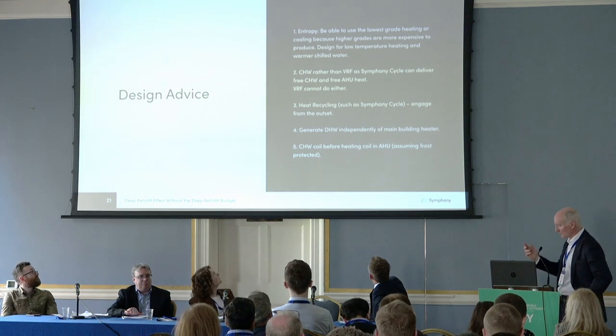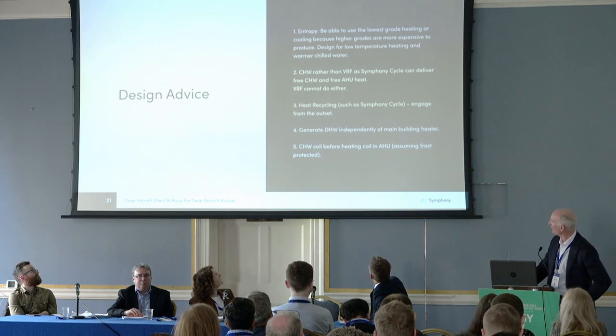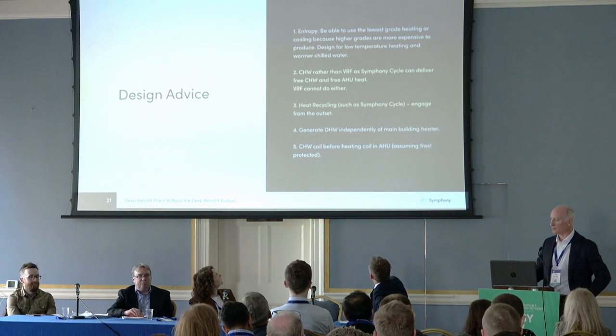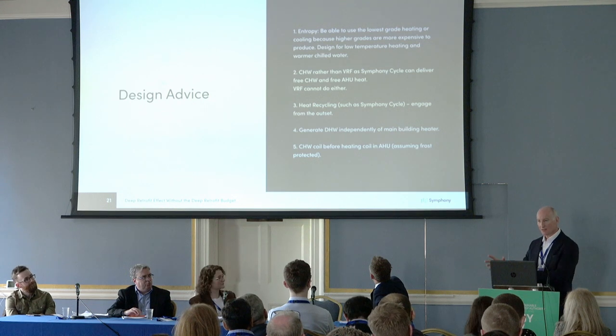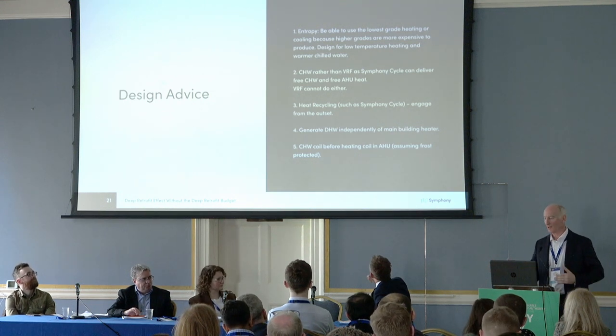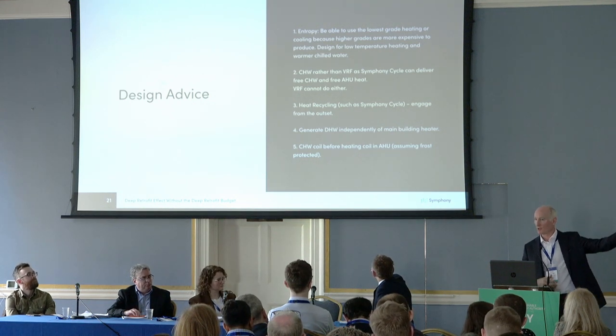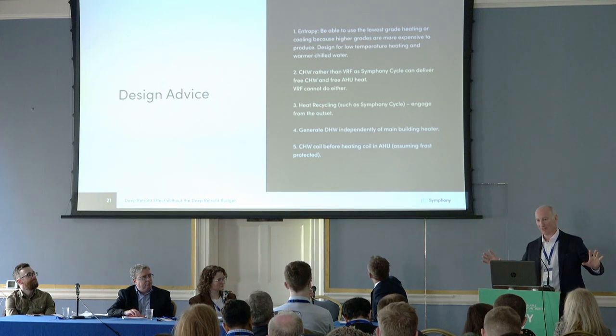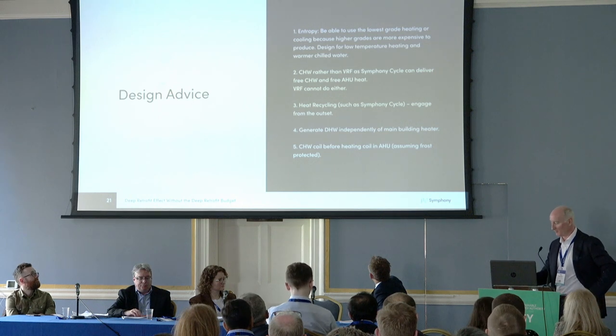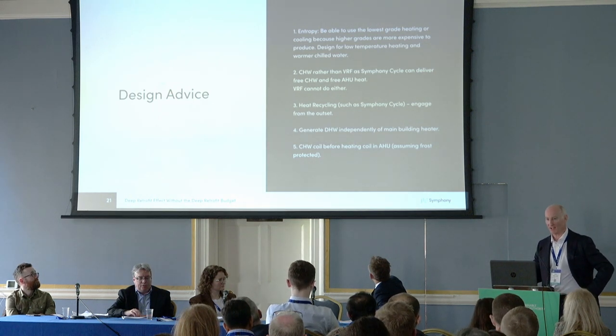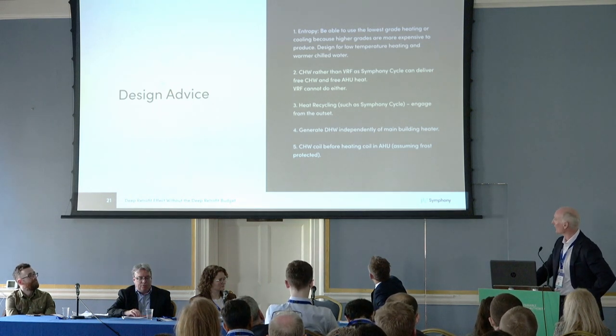Third point, we'd consider heat recycling from the outset. Fourth point, if you've got hot water demand in the building and you've got heating, particularly if it's a boiler arrangement, separate both of them, generate your hot water separately from your heating. Invariably, no matter how theoretically independent they are, we find that it just gets merged together and it's not a particularly good outcome when it's on the same system.